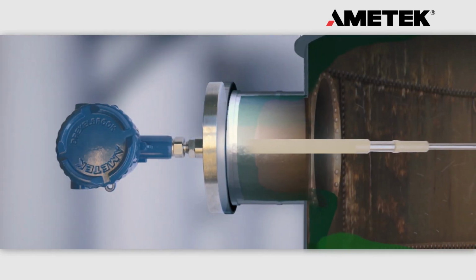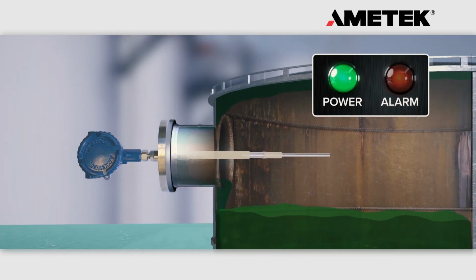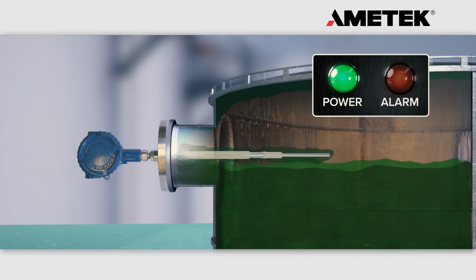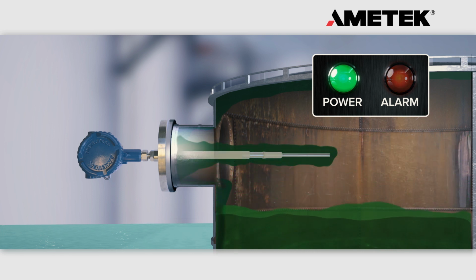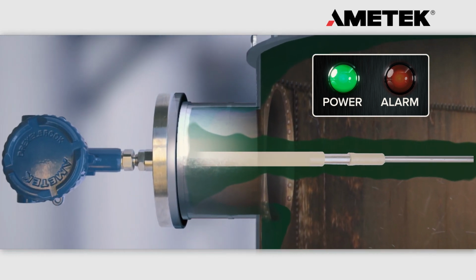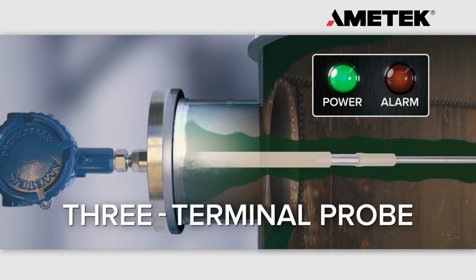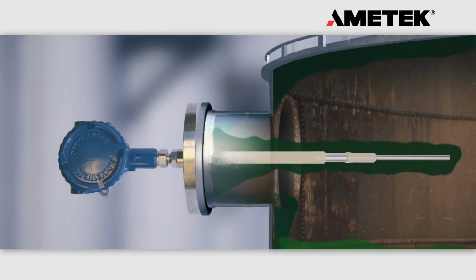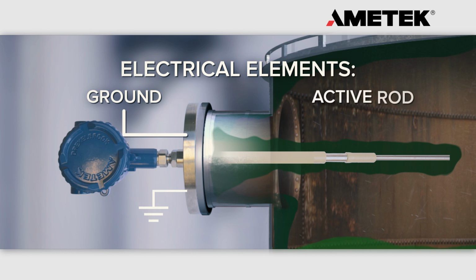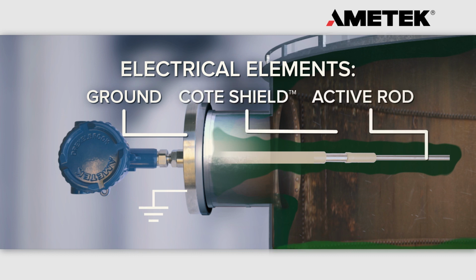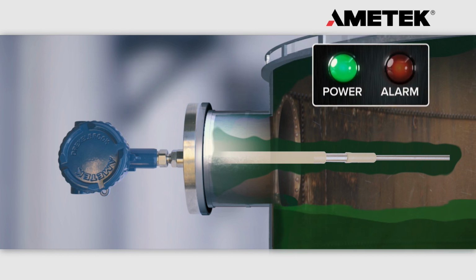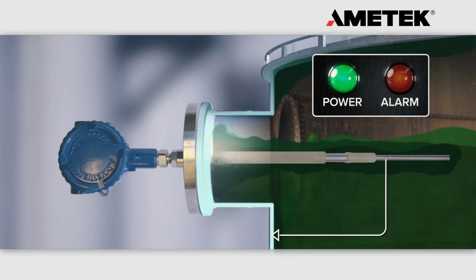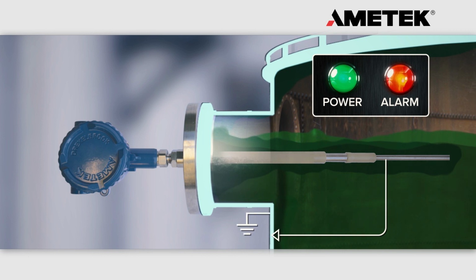Cote-Shield technology allows RF capacitance probes to effectively ignore coatings to prevent false alarms. With Cote-Shield technology, our point-level devices are able to distinguish between a coating and when process media is actually covering the probe. A probe with Drexelbrook's Cote-Shield technology is known as a three-terminal probe. This probe consists of three electrical elements: ground, an active rod, and of course Cote-Shield. When the liquid rises up and covers the probe, an alarm signal is generated just as it would with a two-terminal probe. Now, watch what happens when the process media drops back down.